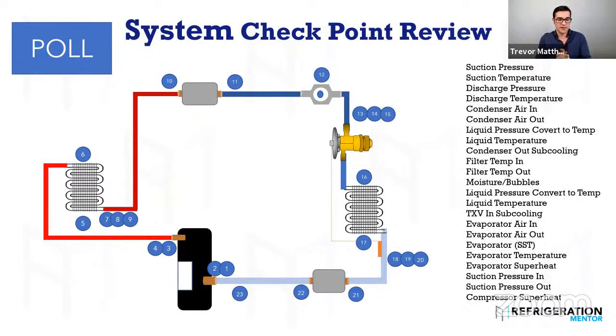All of the above. Poor or loose sensing bulb, and I've seen this a lot. I just don't tighten it properly, or tighten it too much and break the sensing bulb. Okay, plugged or disconnected external equalizing line. That external equalizing line should be downstream, or past the bulb.